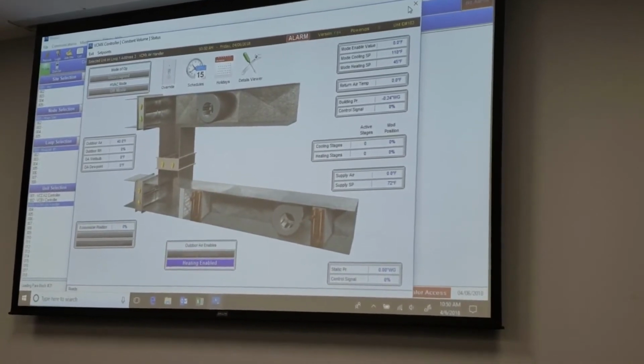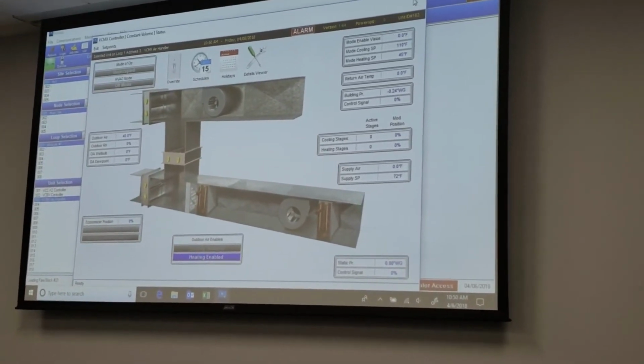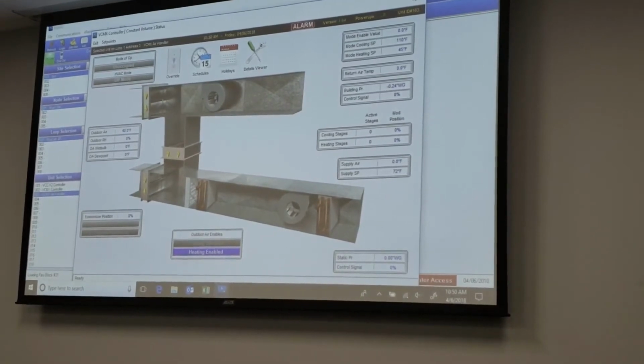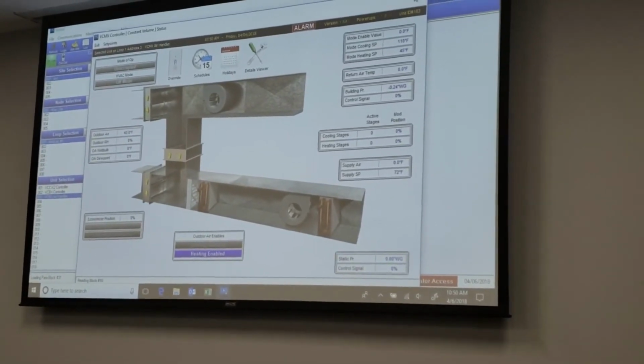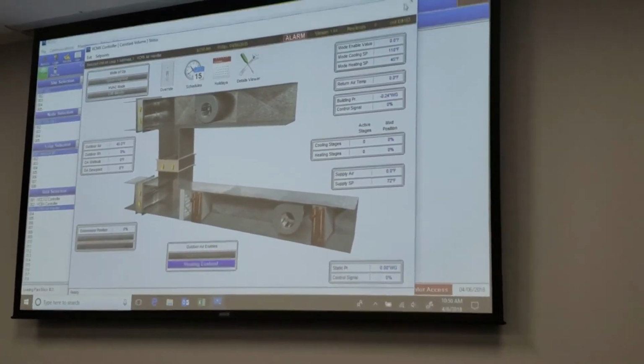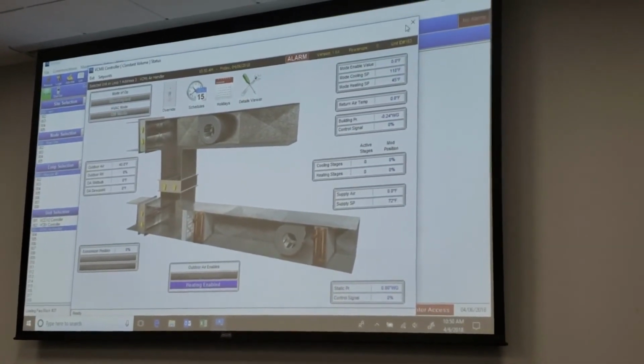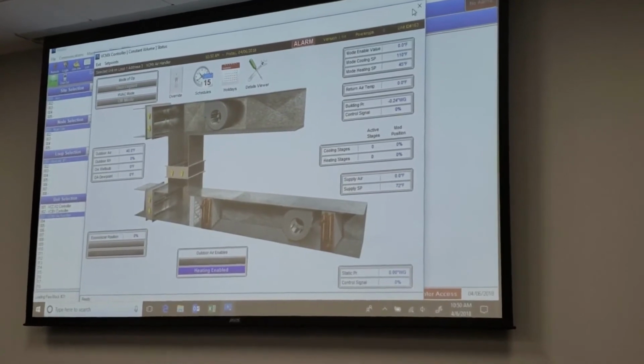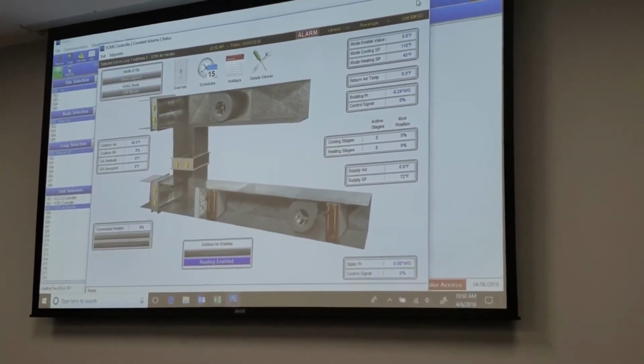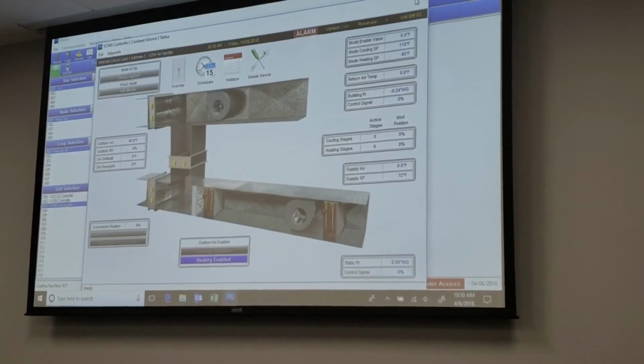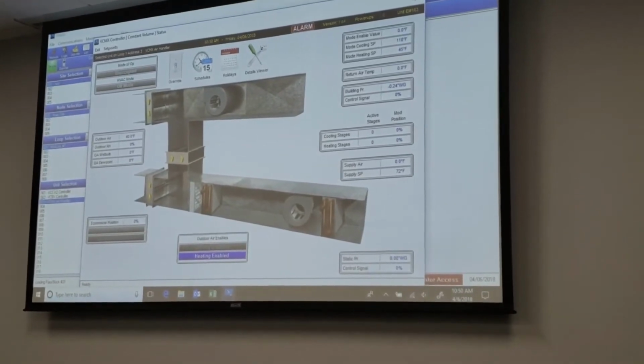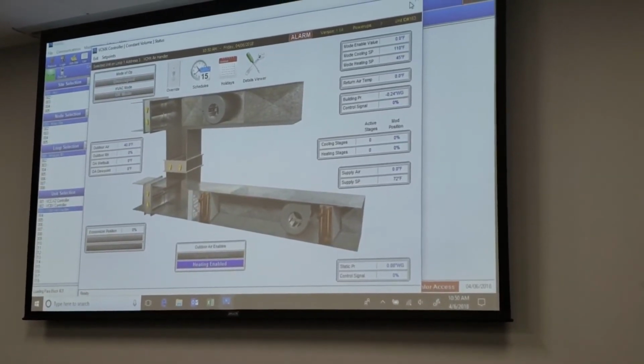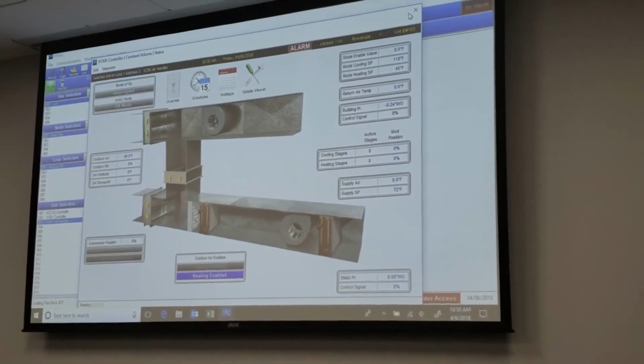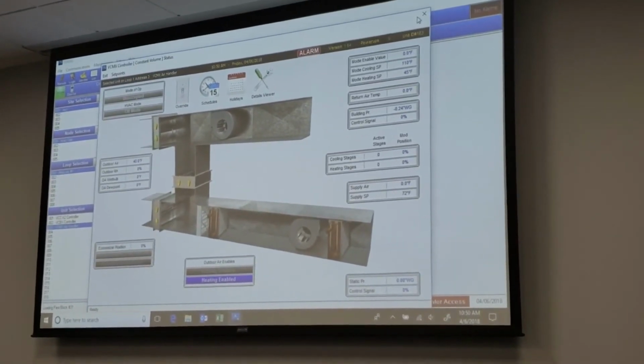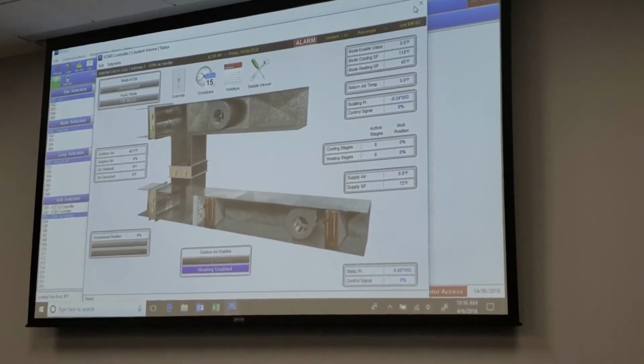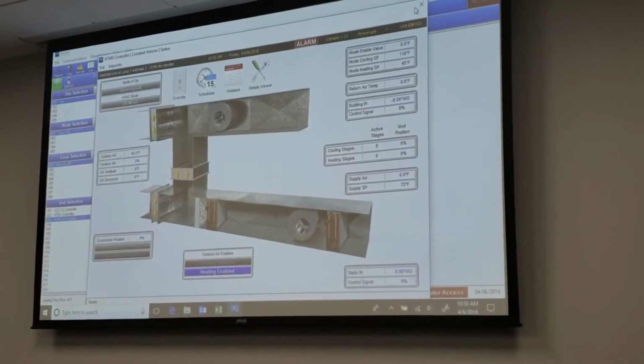Transfer to upload, then you go in and make changes. A bad internet connection takes too long, and they don't want to wait. You can go through and make your changes. Say the set points when you first get there, you go through making changes, you think they're good, you save that set point file. I always do revision 1, and I may have 5 different revisions by the time I leave the job site. I'm tweaking it, the customer's happy, finally, okay, this is where we are.